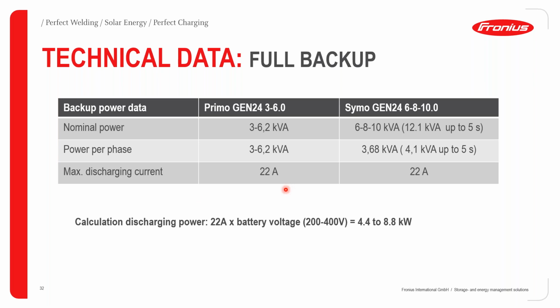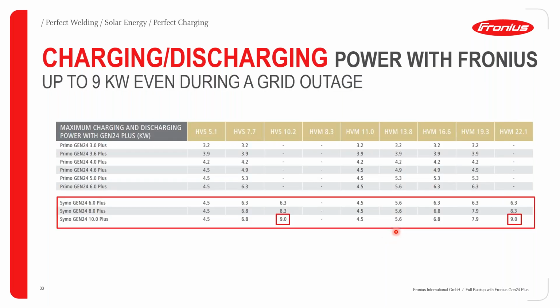So just to throw more light on that, in order to calculate the discharging power, all you need to do is multiply the current by the nominal voltage to get your approximate value of power. So as you can see in this case, for 3-phase, it is 8.8, or approximately 9 kilowatts.